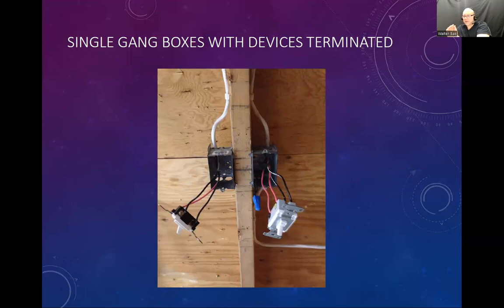If that receptacle is splashed with water, for example, and the water is going to provide a current pathway to the ground from that duplex receptacle, then the current that is being supplied, that's leaving the hot terminal, is going to be bigger than the current that is coming back, because some of the current has escaped through the water to the ground.